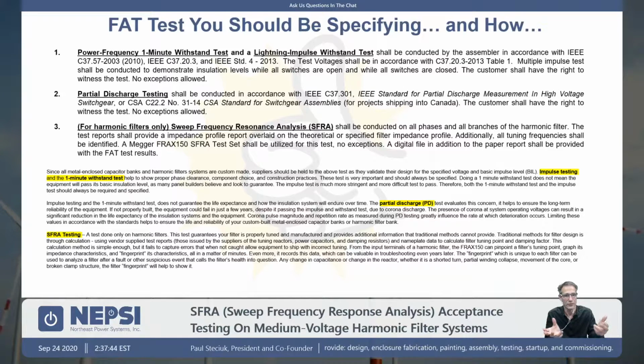When you have corona, you have a degradation in the insulation system. That degradation might take 1, 2, 3, or 4 years to cause a failure, but at some point it will cause a failure. So if you're looking for equipment that's designed for 20-year life, partial discharge testing is something you must specify. And then finally, we did the number 3 item here, SFRA testing.